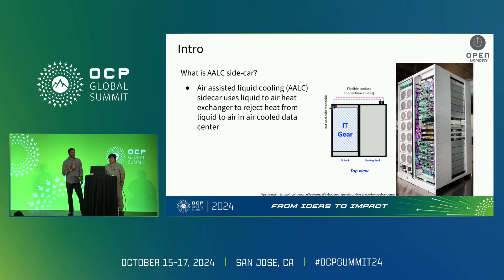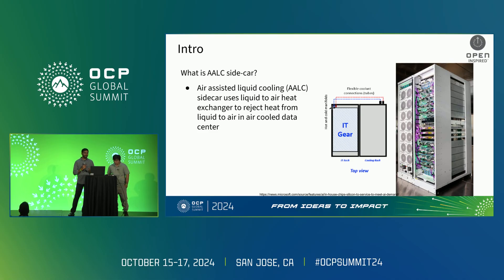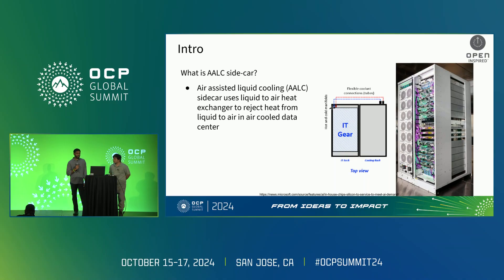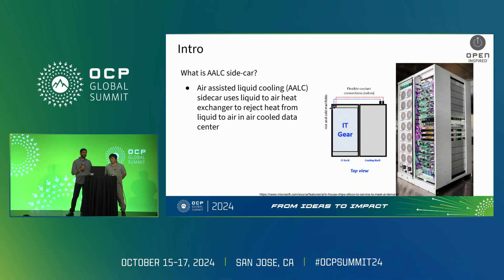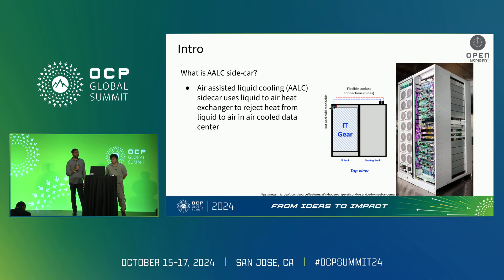So for AALC Sidecar, in this particular track, we're going to talk about how to enable high power density server racks coming with higher 1,000-watt-level IT power at the chip level — how can we enable that using liquid cooling for air-cooled data centers. The Sidecar project's intention is to evaluate existing sidecar solutions, evaluate their performance, and provide guidelines on how to select a sidecar for your particular application, and evaluate how we can extend that capacity for future hardware as power densities at the rack level increase.